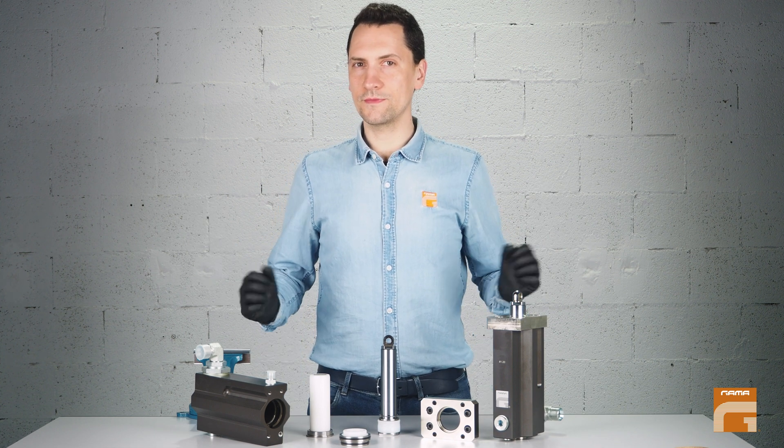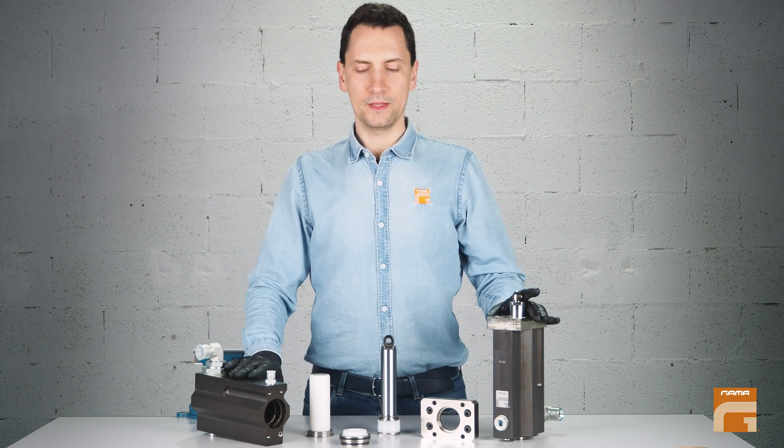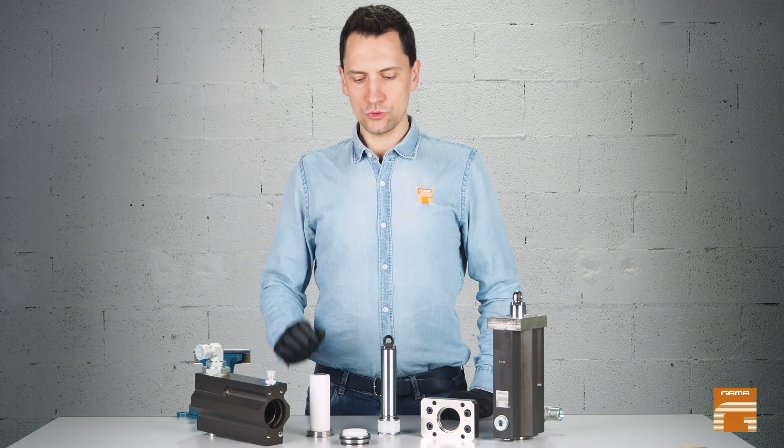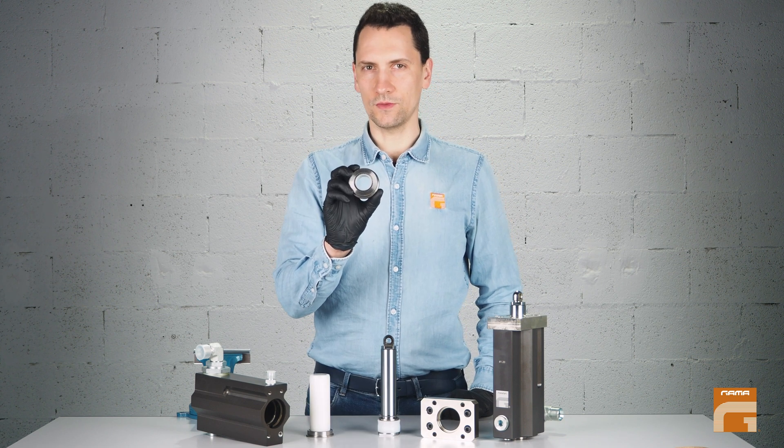Hello everyone! With this technical tip, we finish our series of videos about servicing horizontal dosing pumps. In this video, I would like to show you how to correctly install the static seal of the pump.